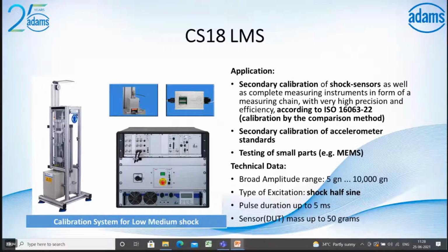CS18LMS, that's a low medium shock calibration system. It's a secondary calibration for shock sensors according to the ISO standard 16063 by the comparison method, and the secondary calibration of accelerometer standards. The maximum you can go up to is 10,000 G, the type of excitation is a shock, and the pulse duration is up to 5 milliseconds.